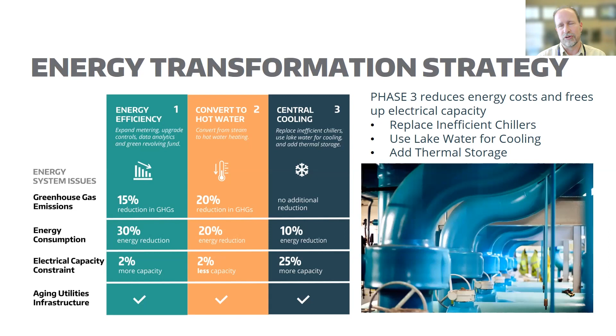Fourth part, electrify heating. I've spoken to using the low-grade heat from the cooling system. There's a challenge in that the timing of using that waste heat is incongruent with seasons. In summertime, that's when the most cooling is happening, so the most waste heat exists, but that's the time of year we have the least heating requirements. We do have some, though. We've got domestic hot water in buildings and showers, and that still needs to happen, so we would still use that low-grade waste heat. We just won't need all of it in that season.